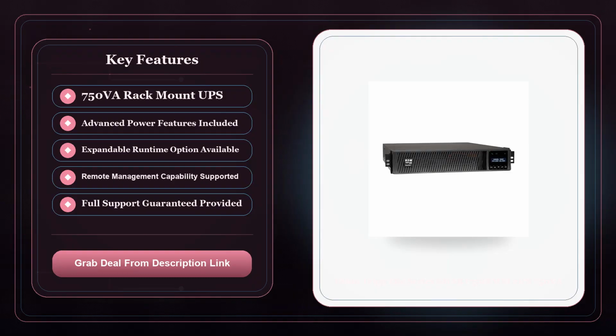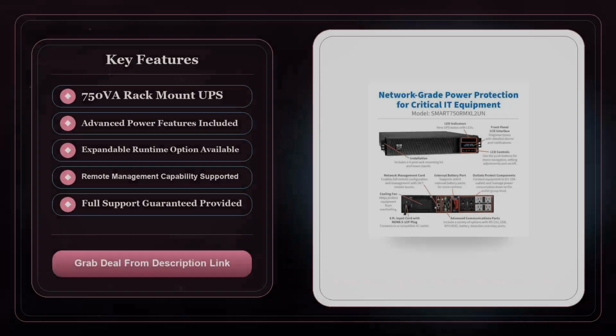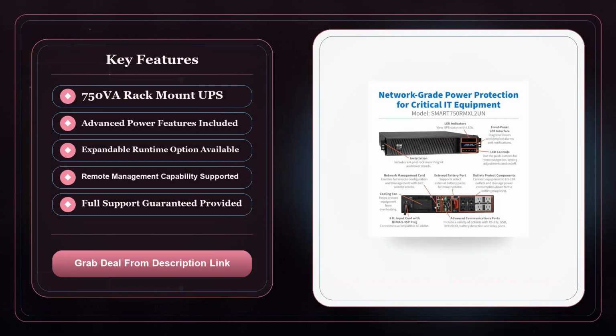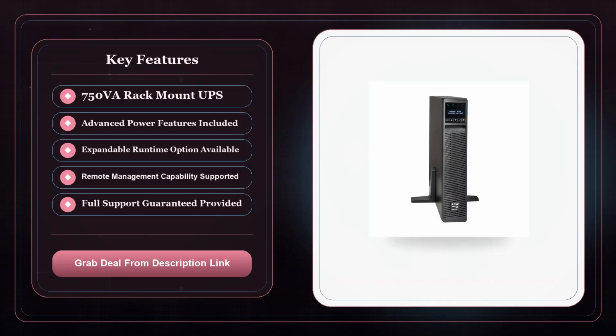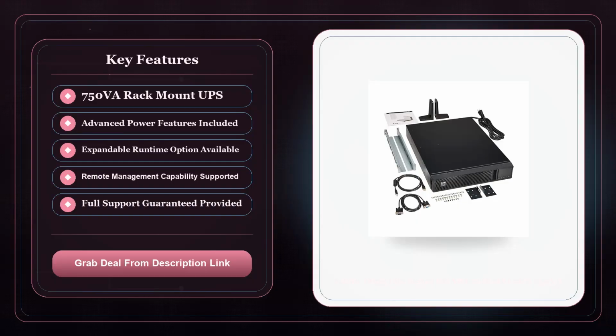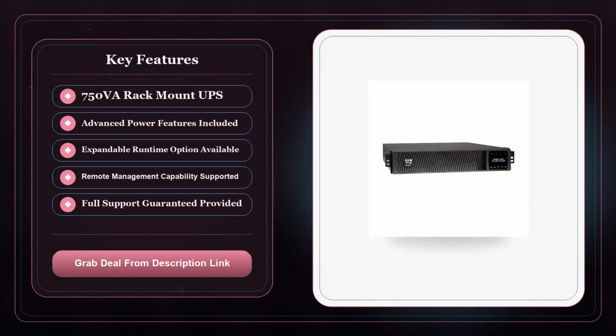Weaknesses are more about expectations than outright defects. The 8 outlets are split between battery-backed and surge-only, and only 4 of them are truly battery-protected. If you plug a peripheral you expect to stay on, like a VoIP phone, into a surge-only socket, you'll be left unprotected during an outage. The unit also lacks a USB Type-C or newer connector for the network card, so you're stuck with the older RJ45 Ethernet port. That's fine for most environments, but may feel dated in a brand new data center where everything is fiber-linked.